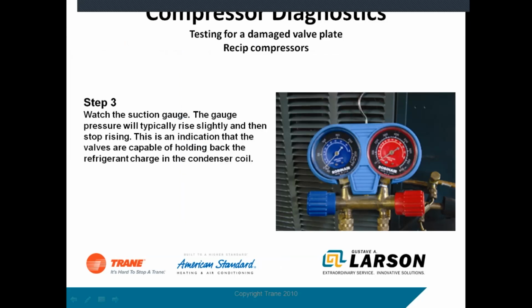So on the old ones, if you wanted to do a pump down test, you could do that. On a recip compressor, you could close the discharge valve, put your gauges on there, pump these down to 0. You could probably pump them into a vacuum. Turn the power off, and the refrigerant charge would just stay in the outdoor unit. If it leaked back out, it probably was a bad valve. That's how you tested the valves on the old ones.